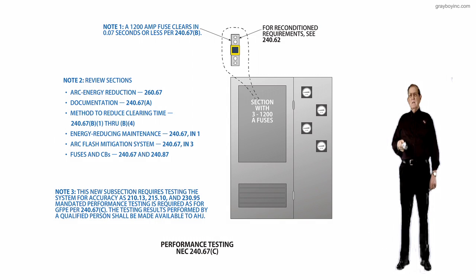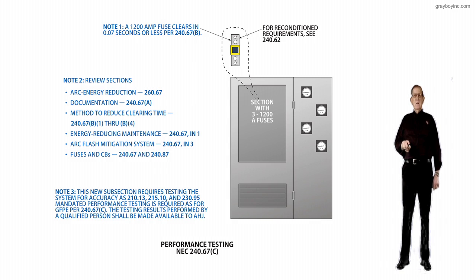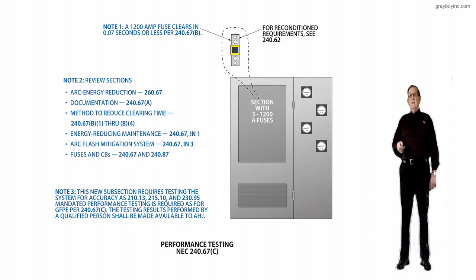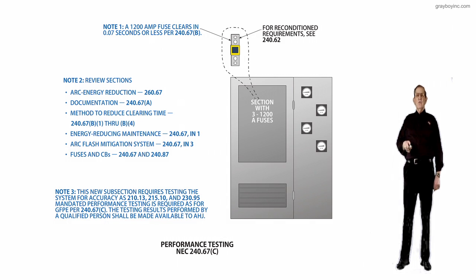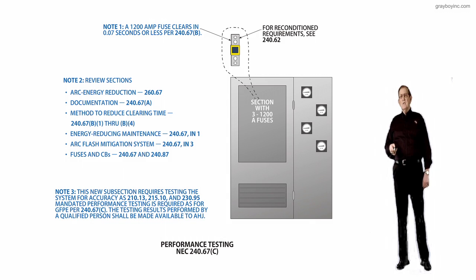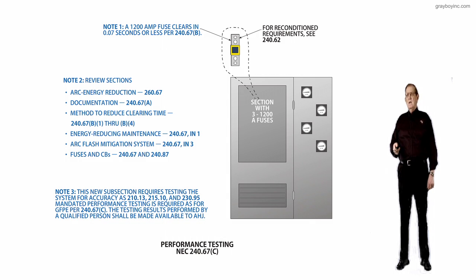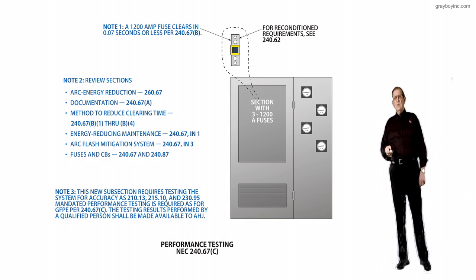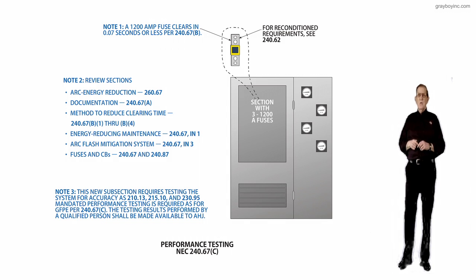The second sentence mandates that only qualified persons are permitted to perform this testing. Additionally, that sentence mandates that the manufacturer instructions be followed if there are any. That is extremely important because the new technologies may not lend themselves well to traditional testing methods. The remainder of the proposed text mirrors that seen in 230.95.